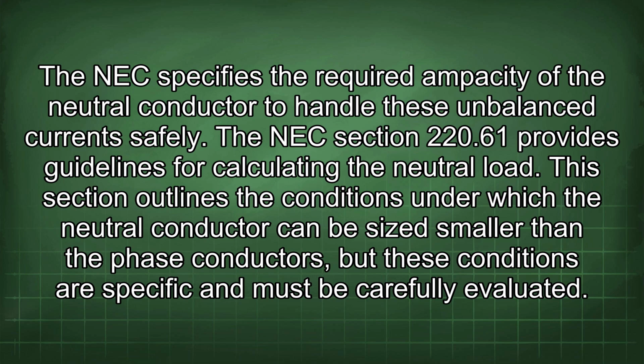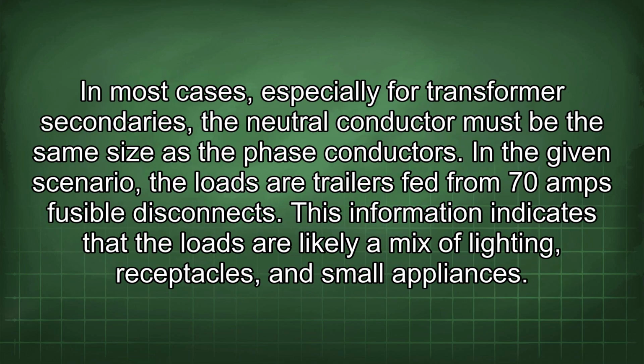NEC Section 220.61 provides guidelines for calculating the neutral load. This section outlines the conditions under which the neutral conductor can be sized smaller than the phase conductors, but these conditions are specific and must be carefully evaluated. In most cases, especially for transformer secondaries, the neutral conductor must be the same size as the phase conductors.